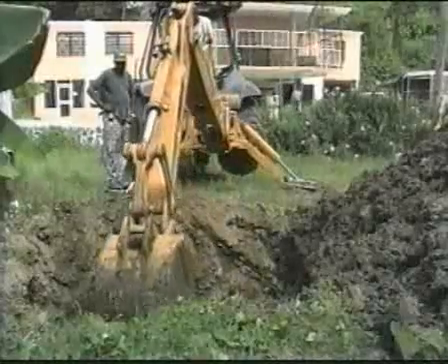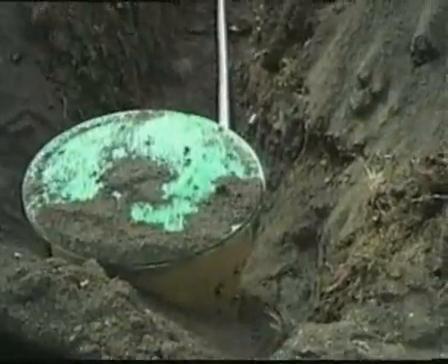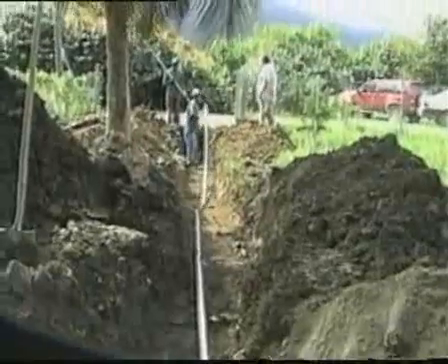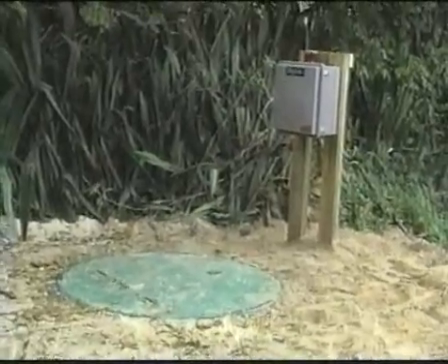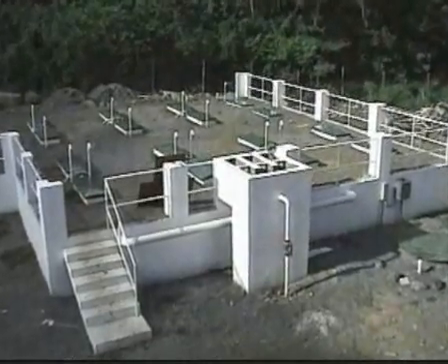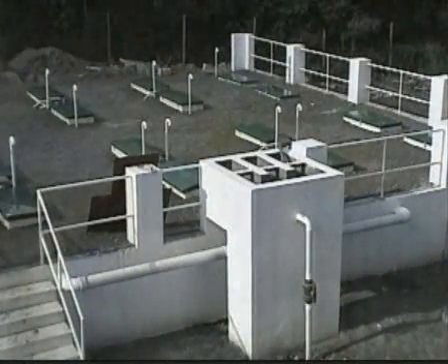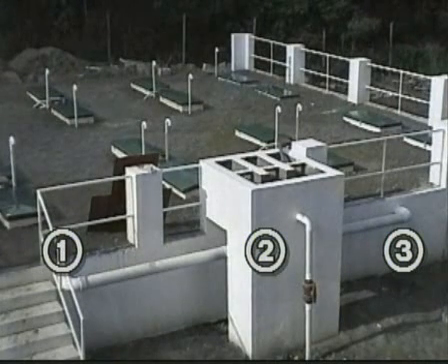Site preparations were initiated with excavation and pouring of concrete base pads on which the Cromaglass batch treat tanks would be located. The Myers-designed wastewater collection system is a low-pressure collection process including gravity sewer lines from the buildings to each of 34 fiberglass pump stations. From here, 3-inch force mains transport wastewater to a splitter box located in front of the Cromaglass treatment modules, which divides the wastewater flow evenly among the three 15,000 gallons per day treatment modules.